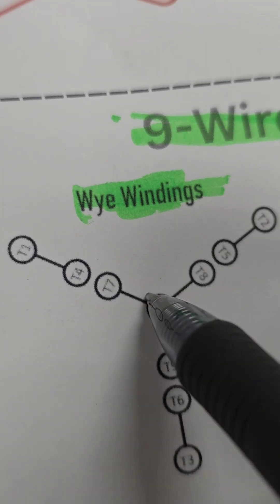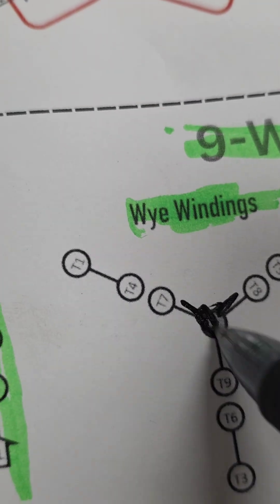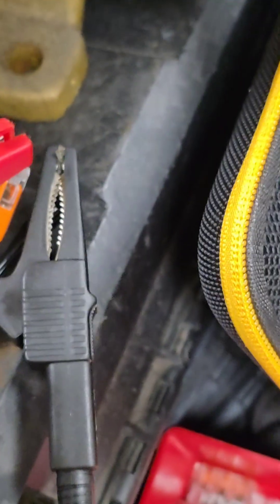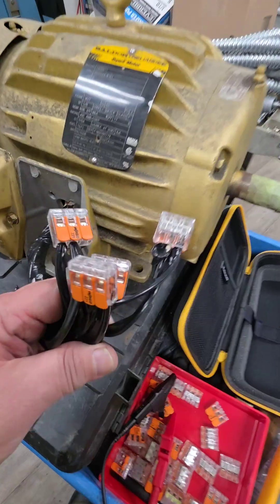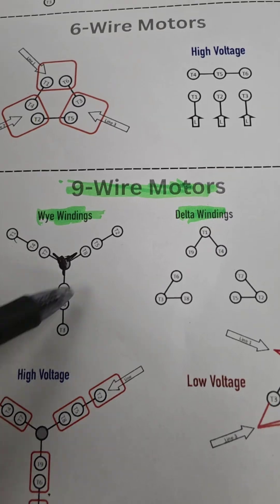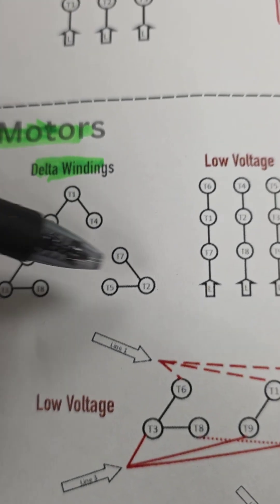At some point there's going to be three wires that read continuity between all three of them, and that's when you know you found the seven, eight, nine in the Y system. Now that you've found those three that have continuity, there should only be six wires left, and those six leftover wires should hold continuity in pairs — giving you four sets of wires, which is exactly covered in the Y system. If it was Delta, it would only be three sets of wires.